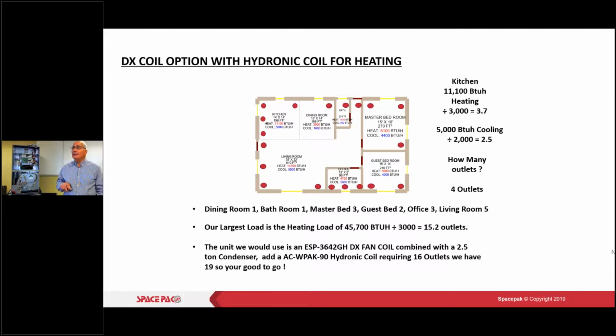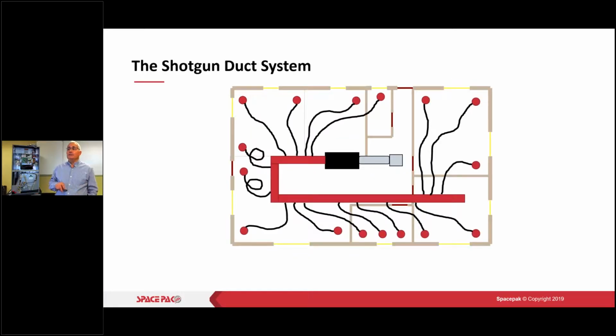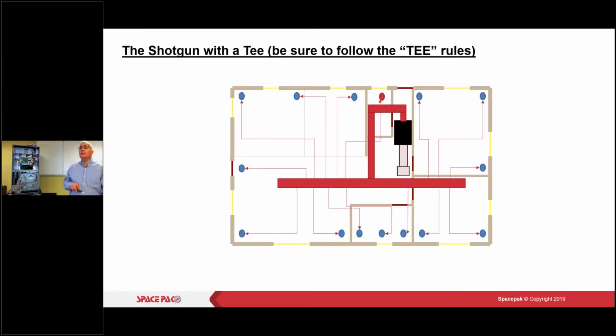So how would we now lay out the plenum? Same floor plan, so a shotgun design here works. Trying to get as much plenum in there as close as we can to the rooms. So that's what that would look like. Could we do it with a shotgun and a T? Yeah, we could, if we're going to put our air handler in this area.